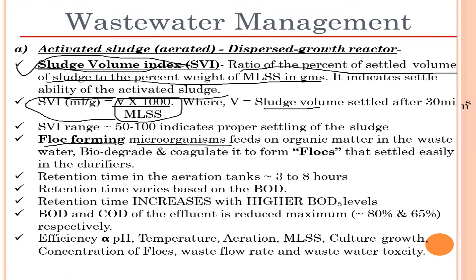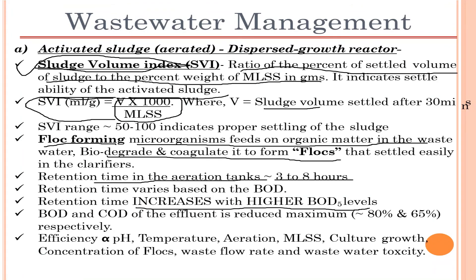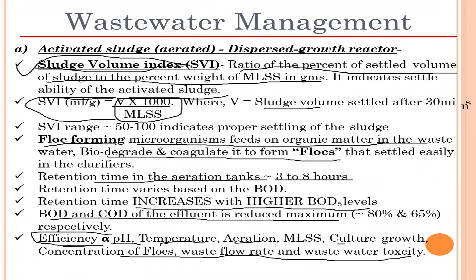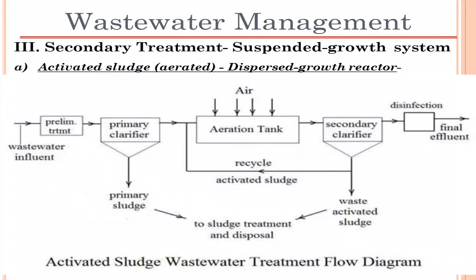Flock-forming microorganisms feed on organic matter in the wastewater, coagulate, and form flocs that settle easily in the clarifiers. Floc formation is important so that matter coagulates, becomes heavier, and settles in the clarifier tank. The retention time in the aeration tank is about 3 to 8 hours and increases with higher BOD levels. BOD and COD of the effluent are reduced by a maximum of about 80 percent and 65 percent respectively. The efficiency of the aeration tank is directly proportional to pH, temperature, aeration, MLSS, culture growth, concentration of flocs, and wastewater toxicity.